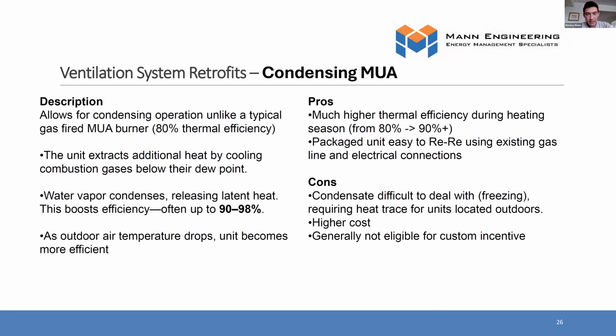The main issue with this condensing makeup air is the condensate. Because the units are typically located on the roof or outdoors, the condensate will freeze. So this is the main complication we have to address when doing condensing makeup air: figuring out a way to prevent it from freezing and potentially causing the unit to not run. One of the ways we do that is with a heat trace system, or if the unit is actually indoors in a penthouse or somewhere else, or potentially we can look at relocating it indoors, then this isn't so much of an issue.